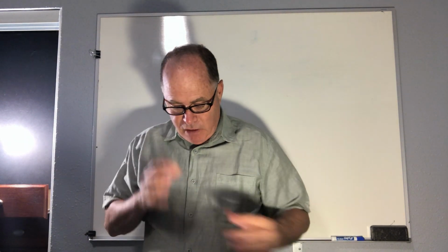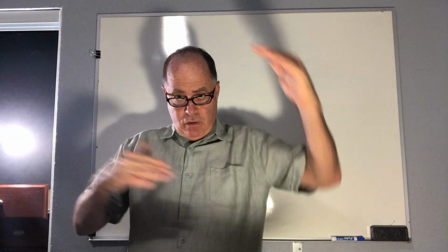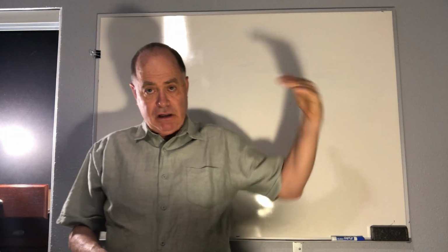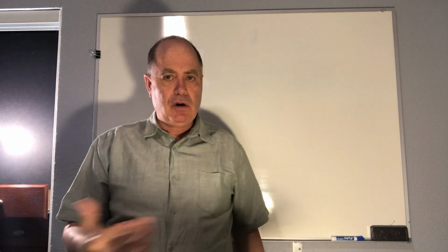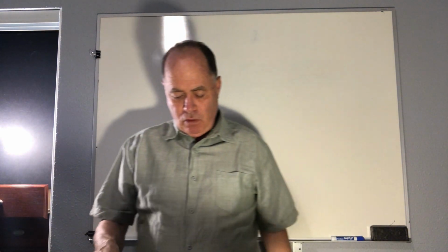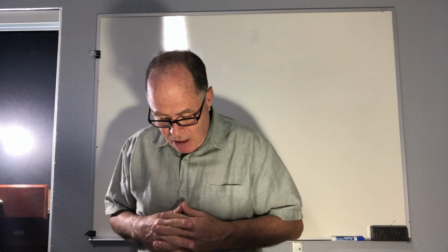All right, let's move on here to access shall be through. Now, to get to ductwork under a house, under a floor, you've got to have 24 by 24 inches, is the code now. Like crawling under a house, you've got to have an opening where you can get under there, maybe bring new ductwork with you, supplies, so that's the standard there. And it's also talking about maybe if you had a trap door to get under, that has to be 24 by 24 inches. And then I gave you a preview about this temperature limit. A furnace supplying warm air to such space shall be equipped with an approved limit control that will limit the outlet temperature to 200 degrees.